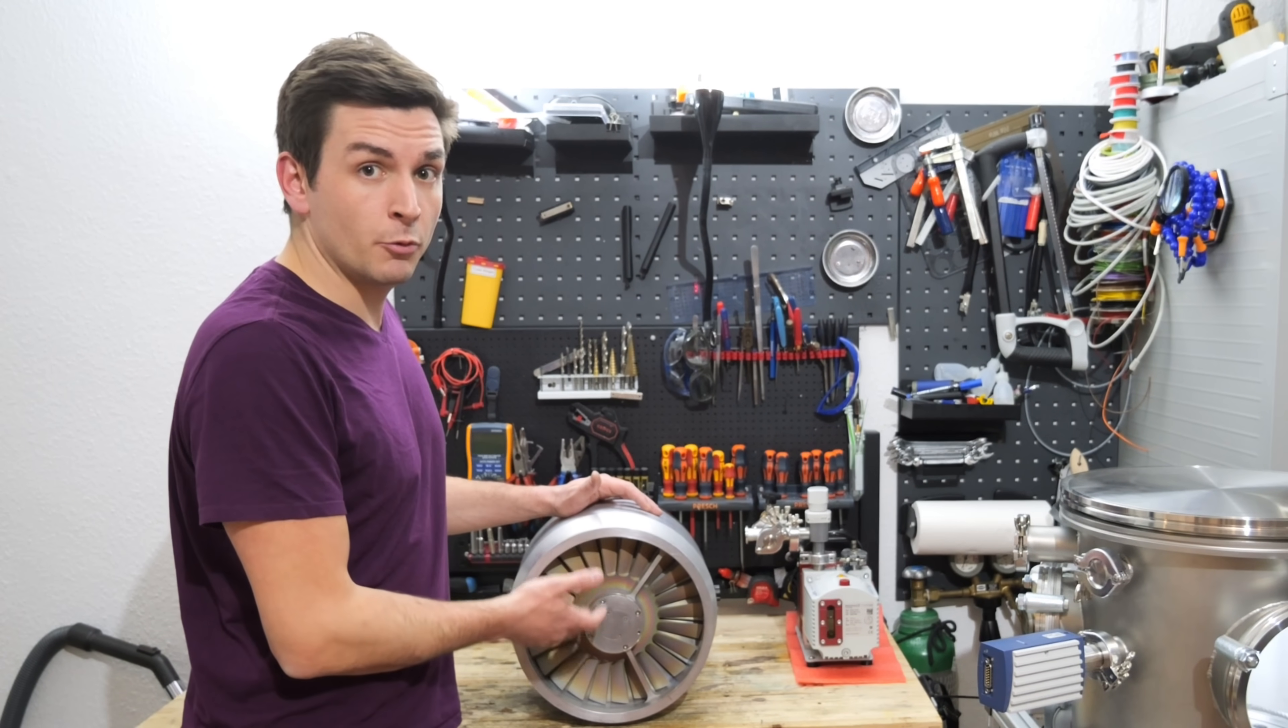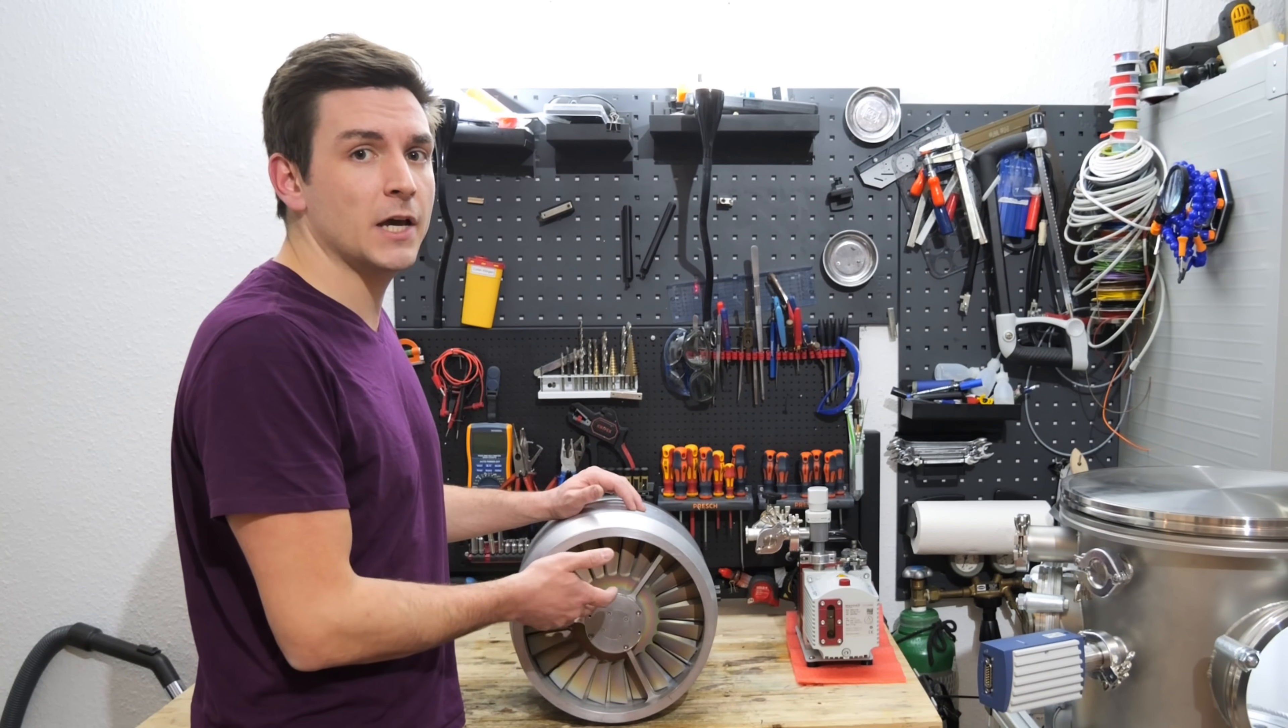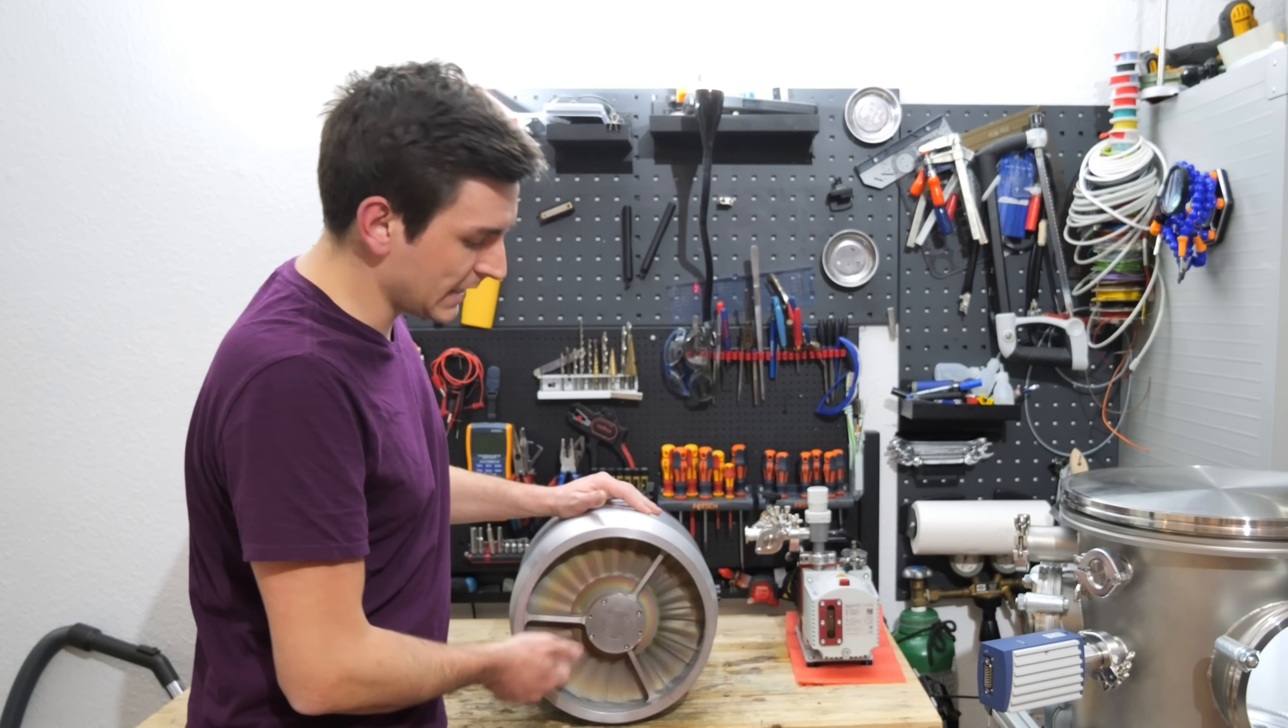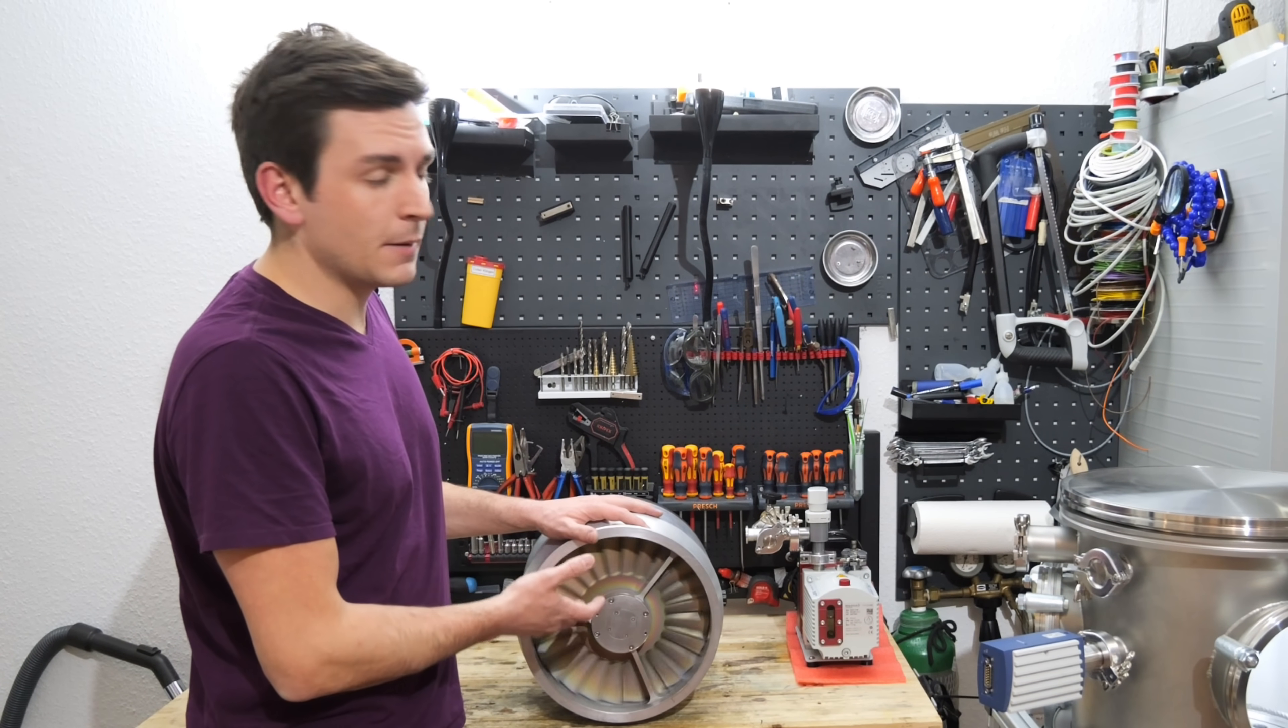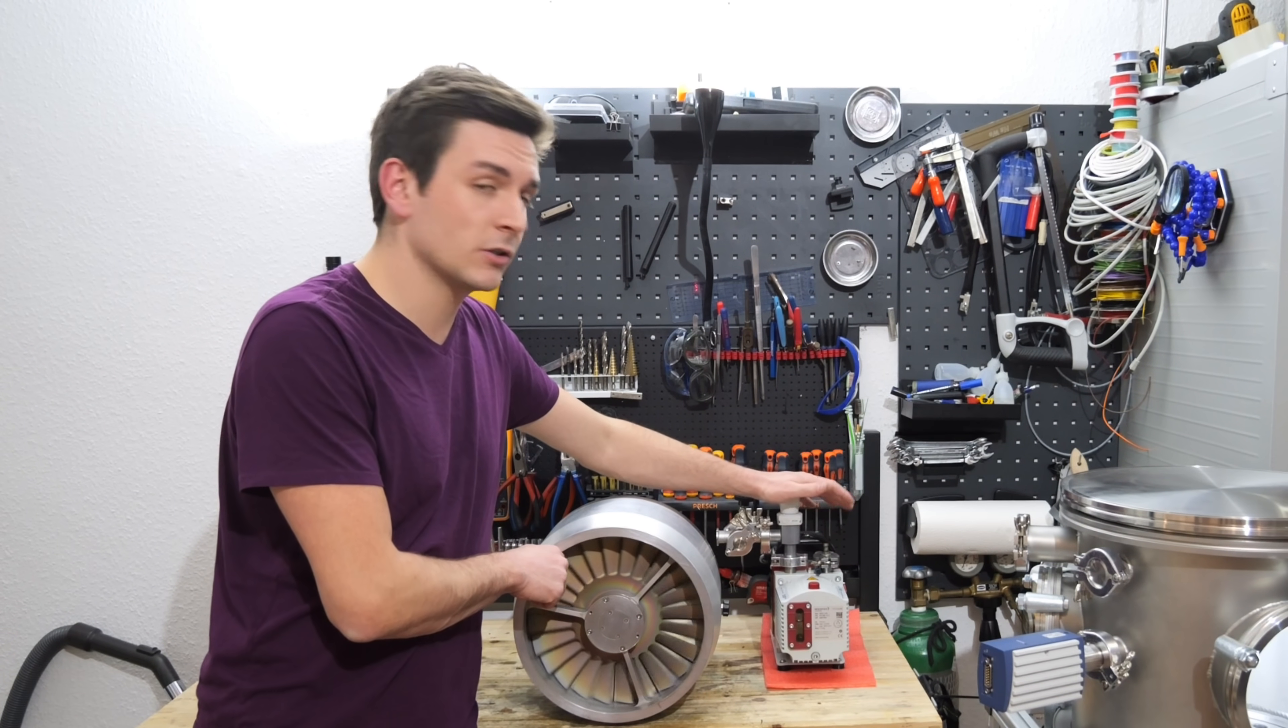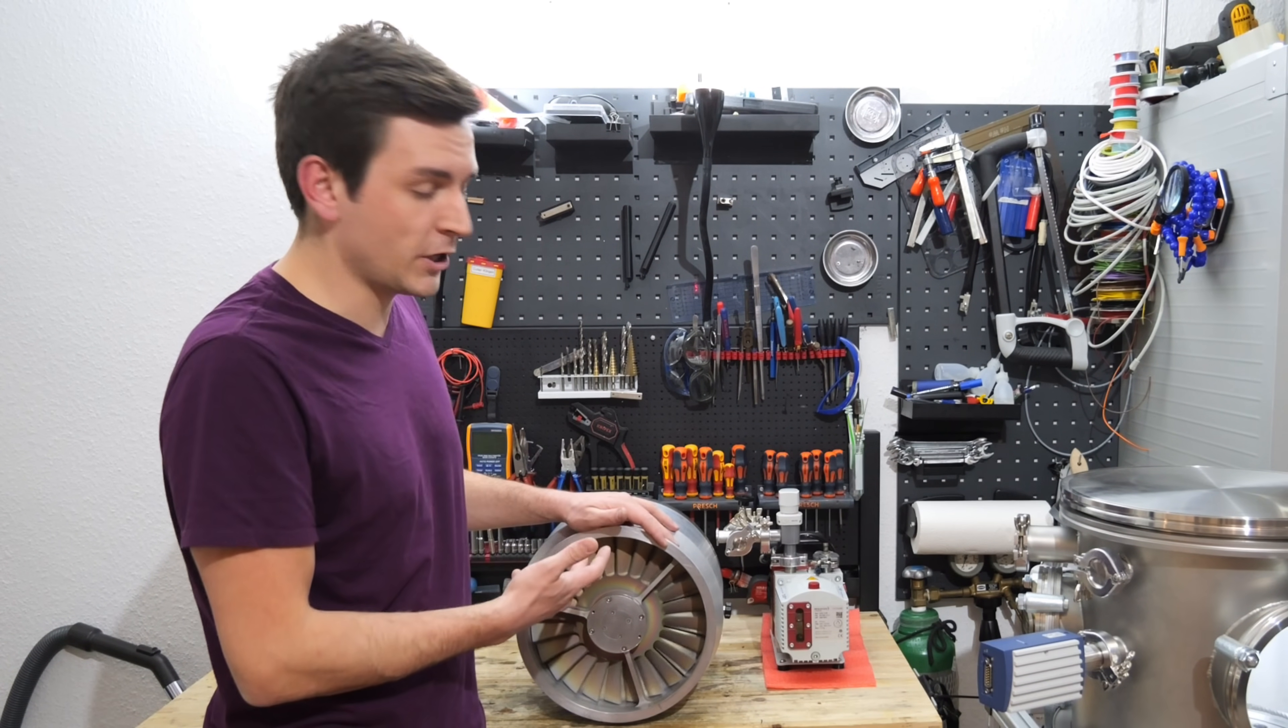This is a turbo molecular pump. In this case it's a Pfeiffer TPH2101, and these pumps are used to create a high vacuum. They're basically the pump you use when a normal rotary vane pump like this one does not suffice and you want to get to lower pressures.